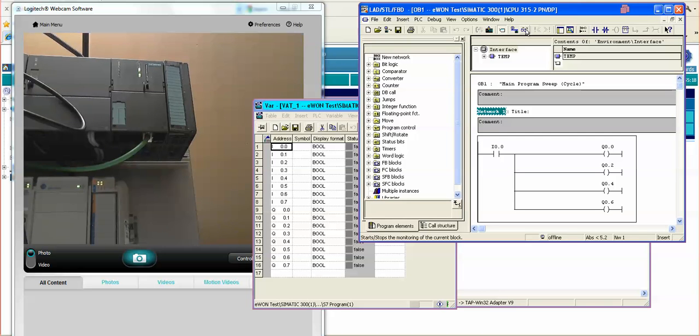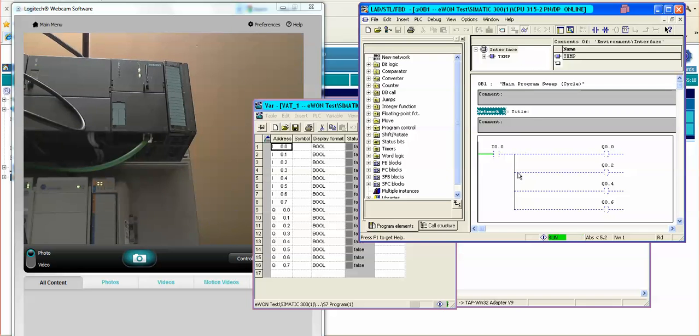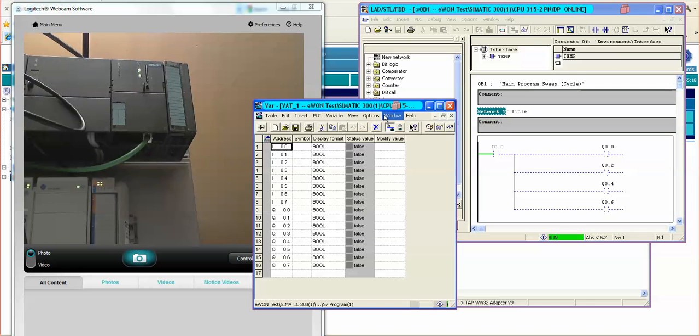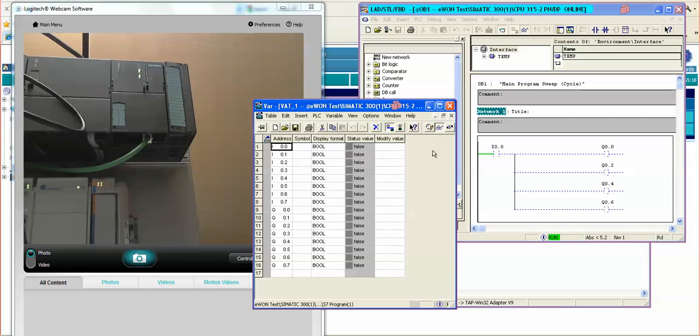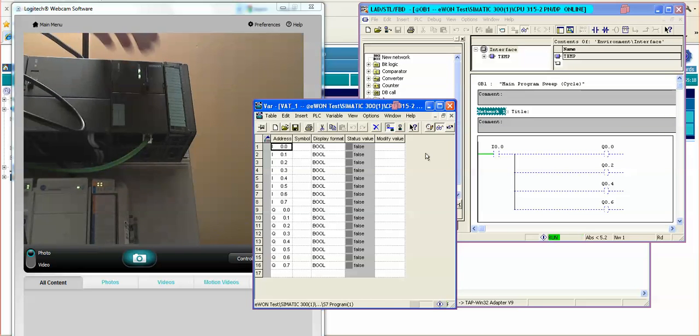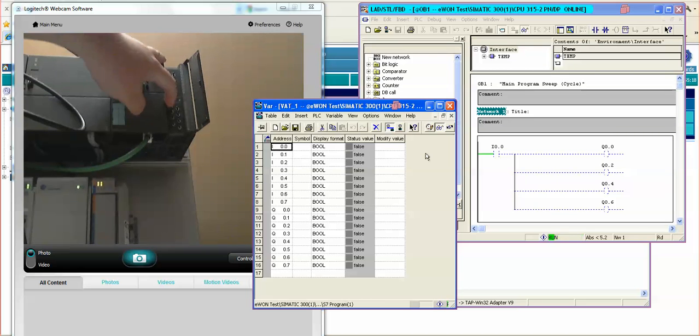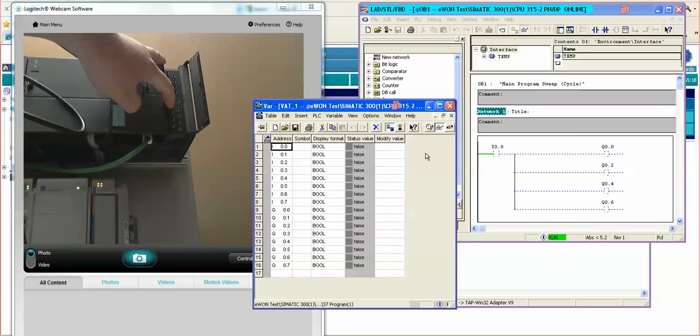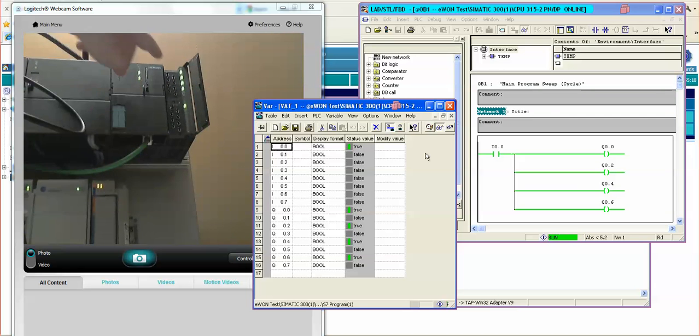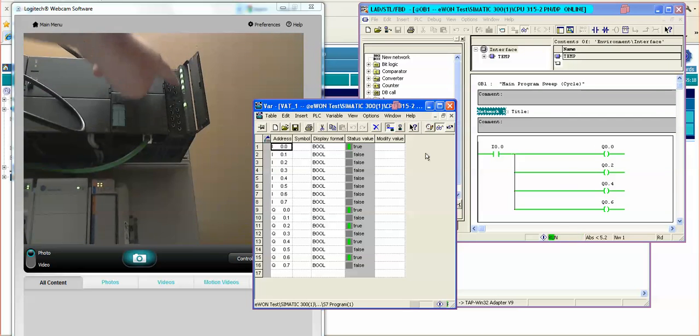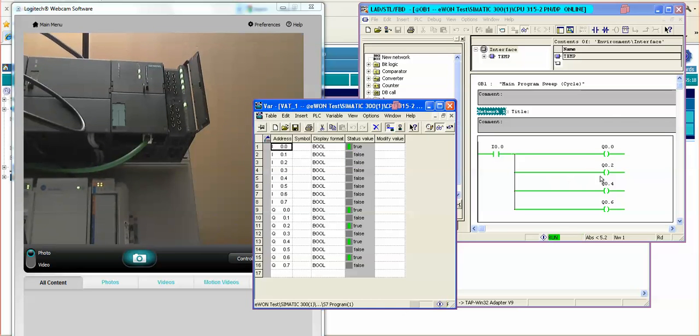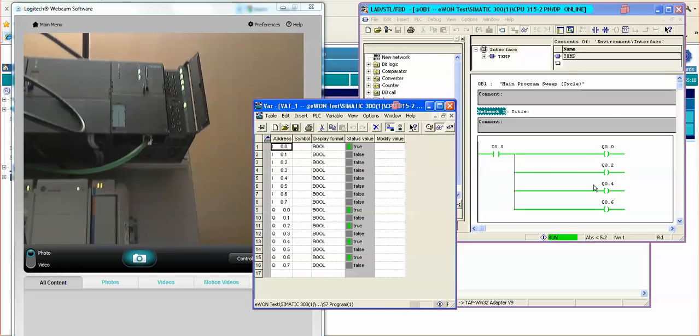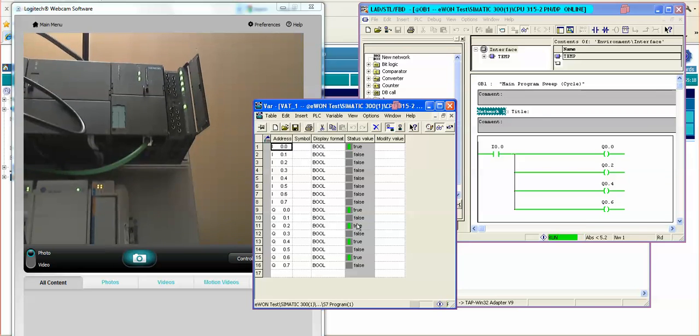I am going to turn on the glasses to turn the monitoring on for the logic, and we should be able to see the status of the logic. The same way, I am going to do the same thing for the variable table, to turn on the monitoring. Now if I open up the little door here and turn on this first toggle switch on this input simulator, I can then see all of these output lights go true as is determined by the PLC logic here. And I see the logic change state or the bits change state in the variable table.